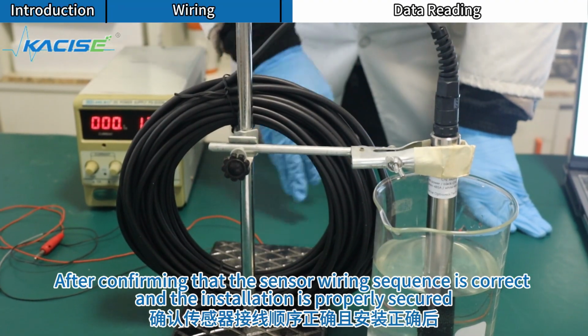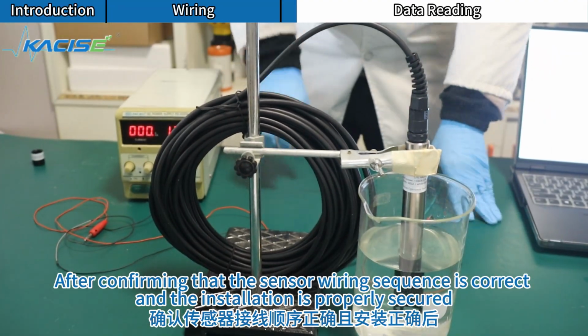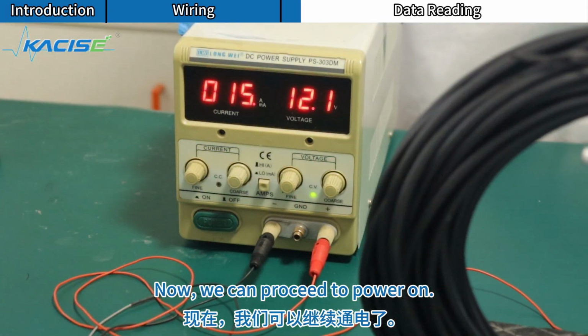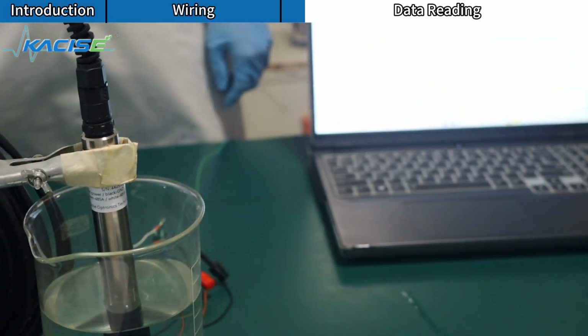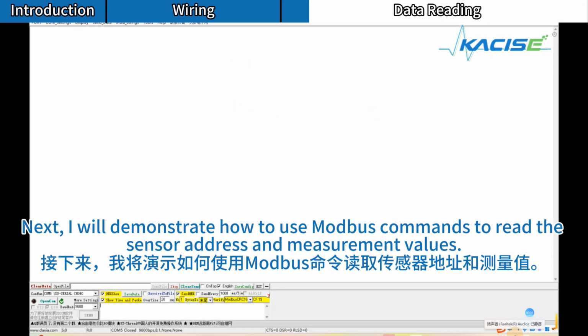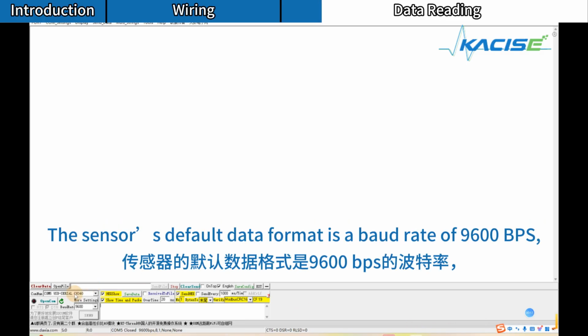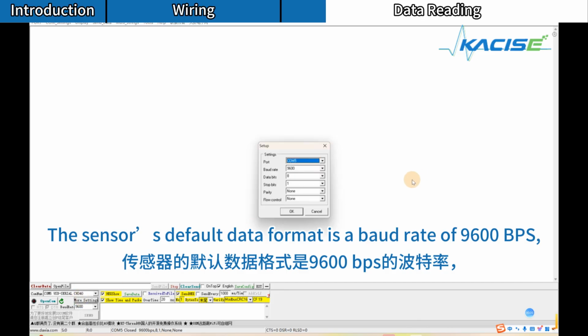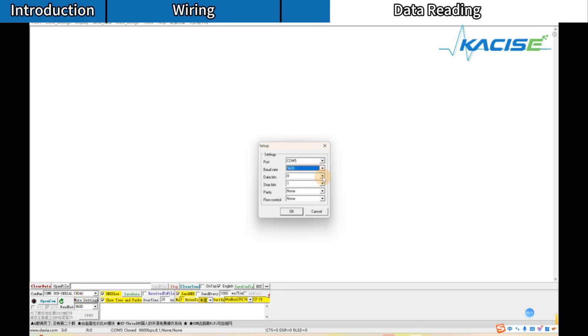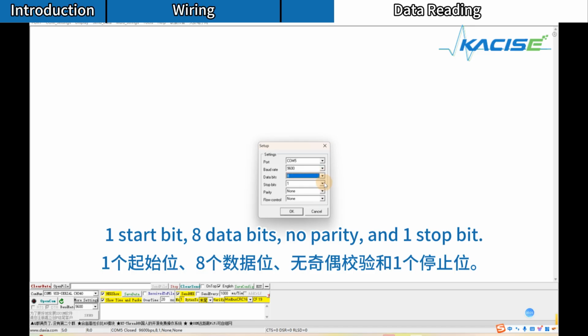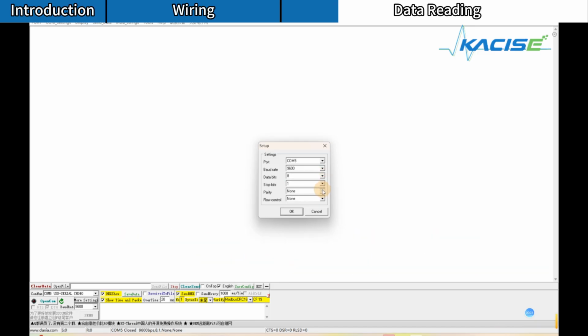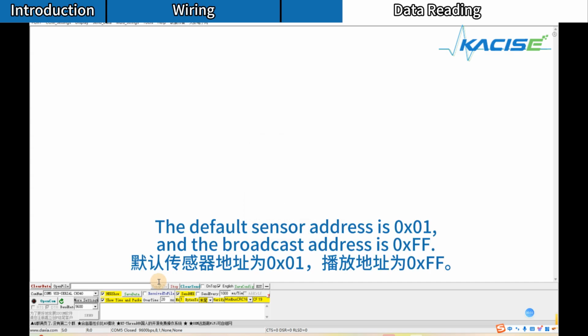After confirming that the sensor wiring sequence is correct and the installation is properly secured, now we can proceed to power on. Next, I will demonstrate how to use Modbus commands to read the sensor address and measurement values. The sensor's default data format is a baud rate of 9600 bps, 1 start bit, 8 data bits, no parity, and 1 stop bit. The default sensor address is 0x01, and the broadcast address is 0xFF.